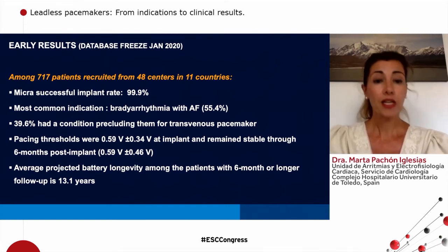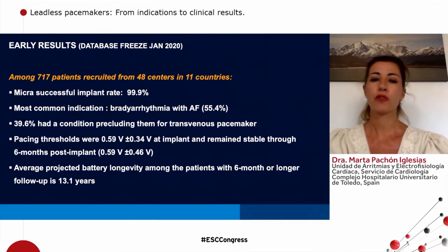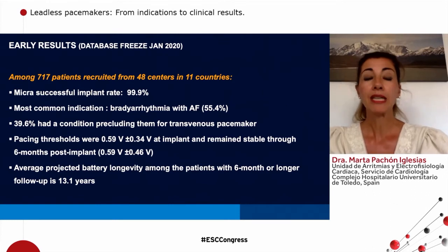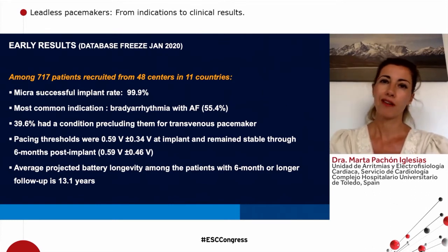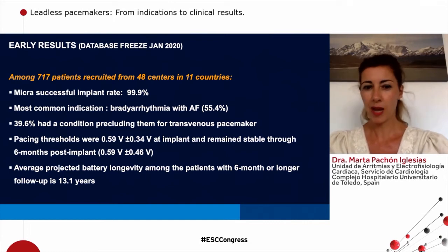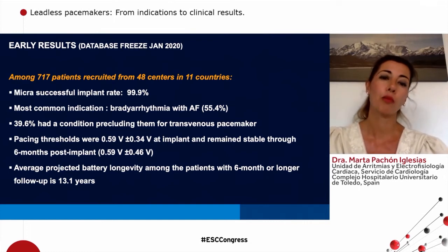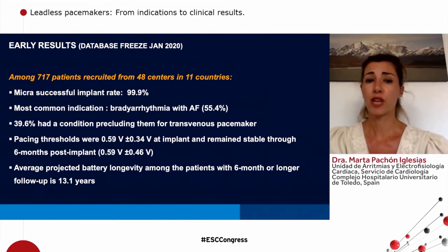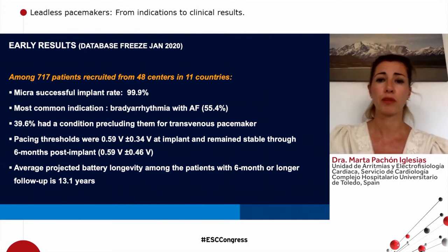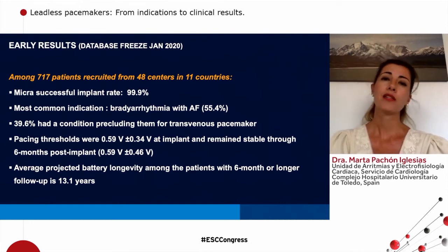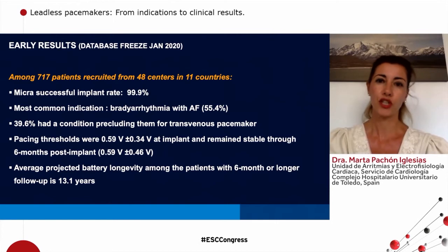The efficacy objective is being met with very low and stable pacing thresholds through the follow-up. Other electrical values are also encouraging, with R-wave amplitudes and pacing impedances both looking good. Finally, the average projected battery longevity among the patients with a 6-month or longer follow-up is 13.1 years.